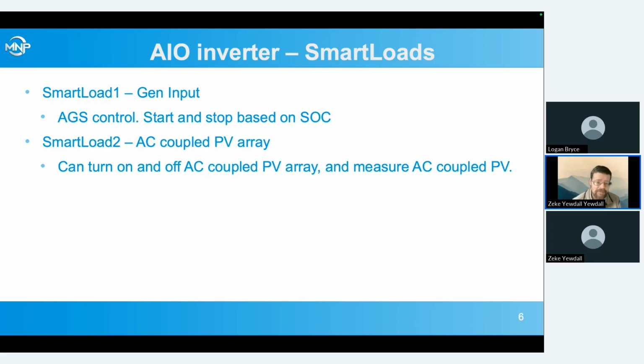Smart load 2, if you set that up for an AC coupled PV array, can independently control that PV array, unlike if you just put it on the AC output of the inverter. It really works a lot better if it can independently control that PV array when it's AC coupled. It can measure how much power is coming in, and it'll turn that AC coupled array on and off as necessary. You can use it off grid and it'll turn the array on and off. It will also do frequency shifting for control of the AC coupled PV array if it's off grid. Obviously, if it's connected to the grid, it can't do frequency shifting because its frequency is determined by the connection to the grid.